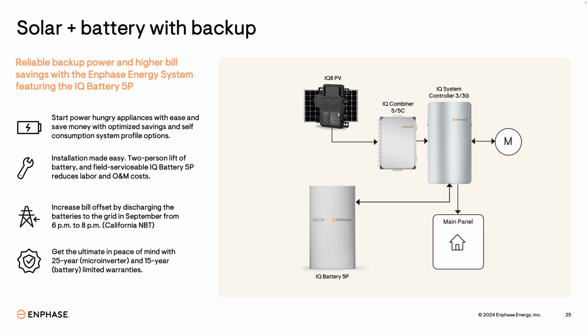If you're connecting into the IQ system controller for backup power, you do need to use the IQ Combiner 5 or 5C. The reason is that there's a limit to the amount of solar that can be connected into the IQ system controller.